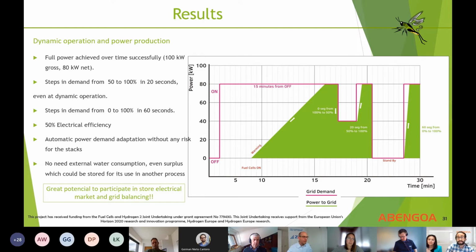Yeah, and this section that you see here in the warm standby is actually the plant running. It has a minimal consumption of hydrogen, of course, but because we only have one electrical interface with the grid, the net power is absolute zero, which is great if, for example, in some areas with electrical congestion, DSOs tell us that they need to shut down specific power generation immediately. So we also show this capability here.